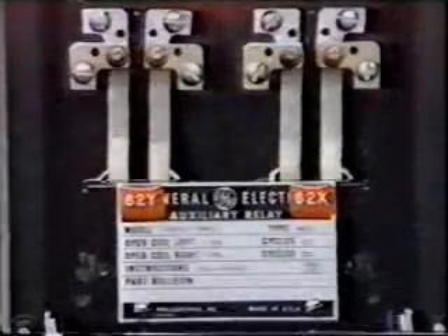specification. In some types of relay, particularly solid-state relays, it may not be easy or even possible to mechanically operate the relay contacts. One way around this problem is to simulate the output signal by isolating the relay and injecting the appropriate DC voltage into the output circuit.